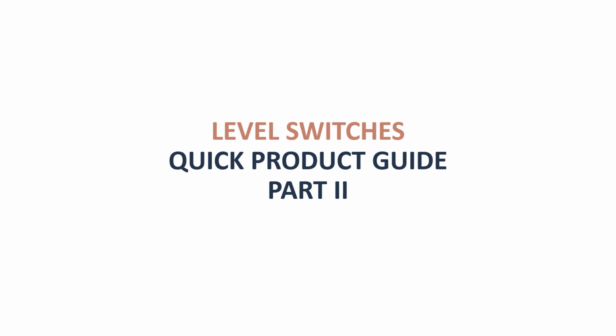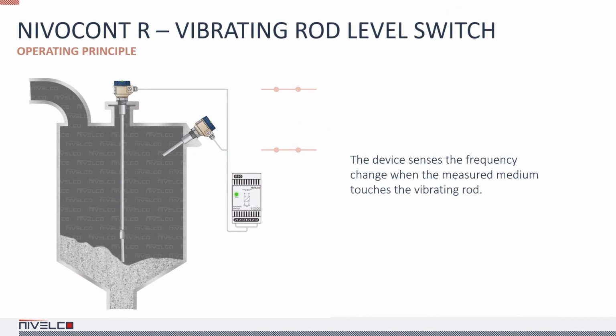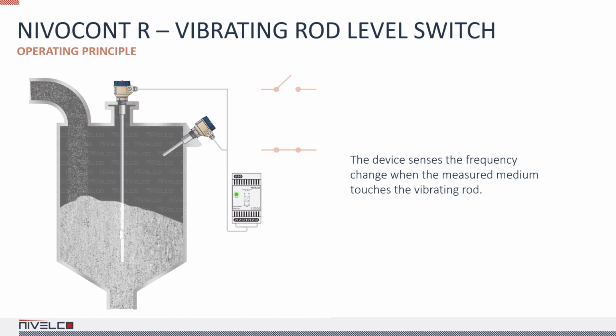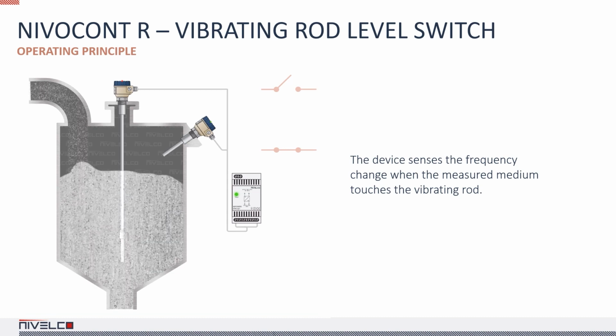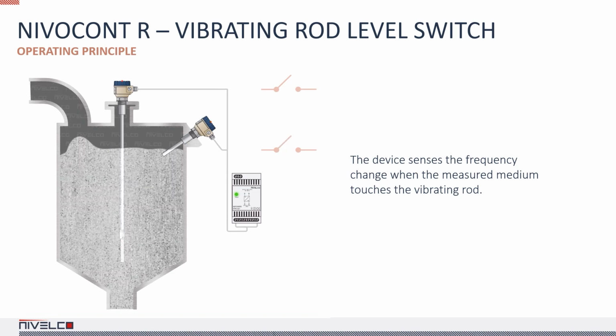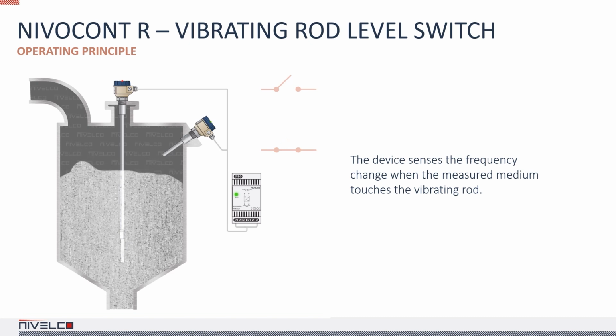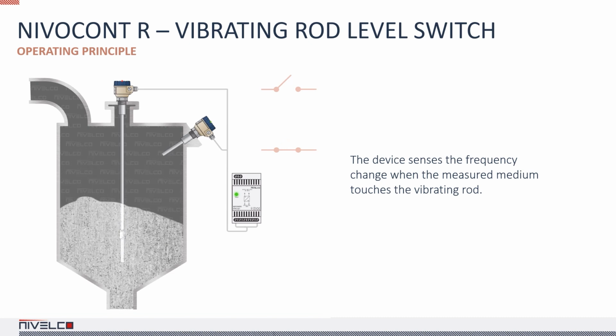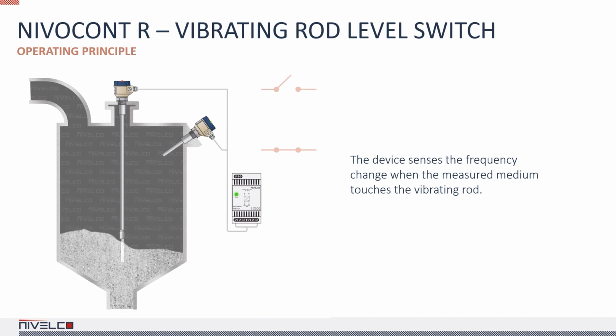Today we're gonna continue discussing level switches. The NIVOCONT R vibrating rod level switch is designed for high and low level indication, granules and powders with a minimum density of 0.0289 ounces per cubic inch. It controls the filling and emptying of tanks, silos and hoppers, and it can send out an alarm signal when necessary. The circuit induces vibration in the probe.